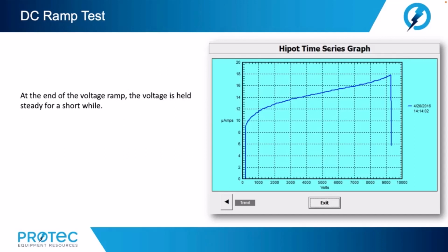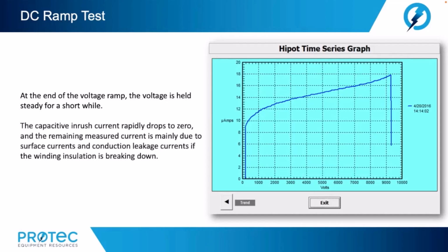At the end of the ramp voltage, the voltage is held steady for a short while. The capacitive inrush rapidly drops to zero, and the remaining measured current is mainly due to surface currents and conduction leakage currents if the winding insulation is breaking down.